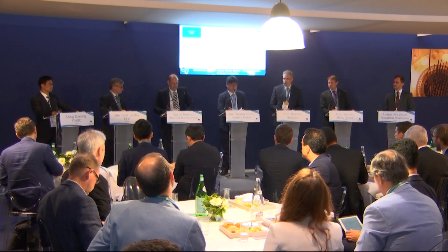Mr. Song? Yeah. The costs of electricity generation differ country by country and area by area where the plant is constructed. For example, the cost of an LNG plant may be different depending on where the plant is located. If the location needs high cost for LNG transportation, the electricity generation cost will be high. SMR may be competitive for isolated areas, and also it may be competitive if a lower construction cost can be achieved by a mass production concept using the same design. The passive safety system is also helpful to reduce the construction cost because many safety class active engineered safety features are not required or can be replaced by non-nuclear safety class equipment.